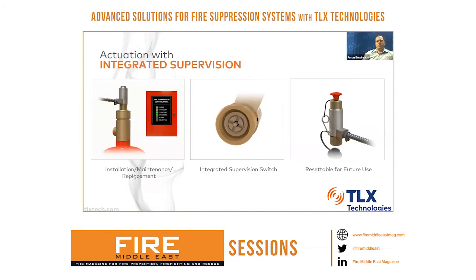So moving over to the second slide, the integrated supervision switch, you're probably wondering, how does that happen? If you notice around the firing pin, there's a slotted circular component. And basically what we do is there's a normally closed switch in there. When the solenoid actuator has been placed back onto the discharge valve appropriately, the threaded boss on the top of the system depresses, or compresses that switch, which allows that signal to open up and then turns the visual signal off at the control panel.